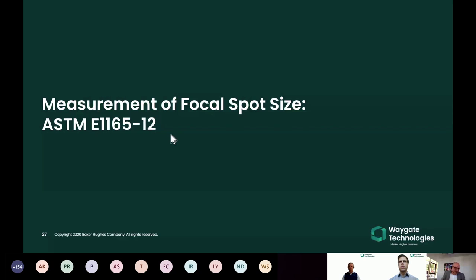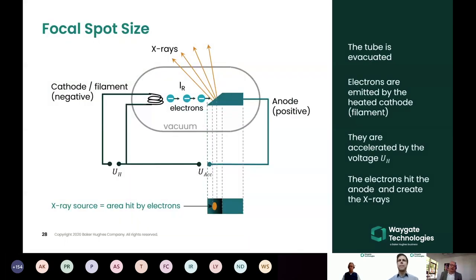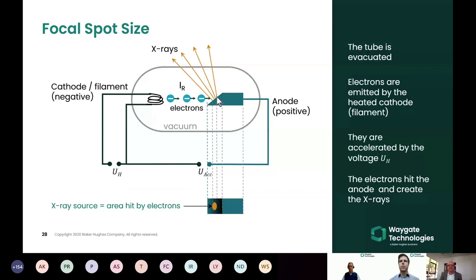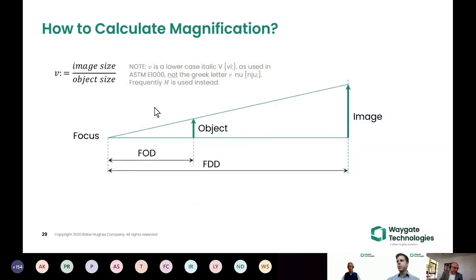Now we look at the focal spot size of the tube, which also contributes to unsharpness. In a simple X-ray tube, electrons from the filament hit the anode target, creating a spot from which X-rays are emitted - this is the focal spot, and its size defines the X-ray source size. Measuring this is difficult; you cannot directly observe it, so we need an indirect method.